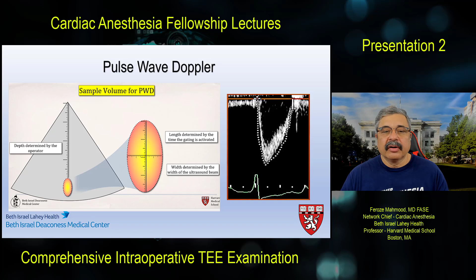You identify precisely where the Doppler shift is maximally occurring, but there's a certain price to pay for that, and that price is the likelihood of aliasing, and we'll get to that in a second, and how pulse wave Doppler is susceptible to aliasing. But to recap, the depth of the sample volume, the location, and its width and its length are determined by the operator to know exactly how much of an area needs to be interrogated for ascertaining whether the flow is coming towards or away from the transducer.